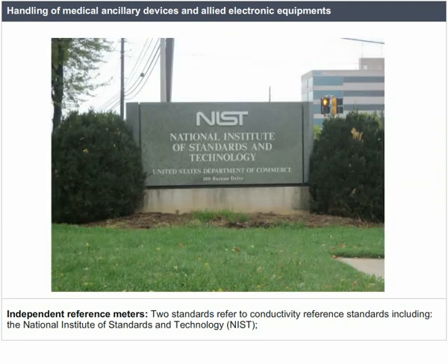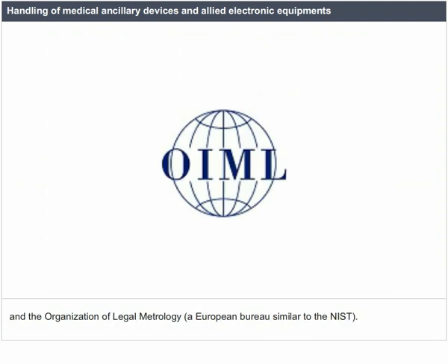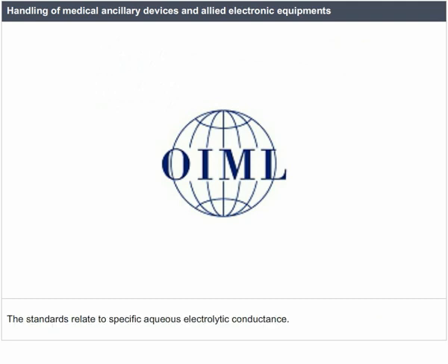Independent reference meters. Two standards refer to conductivity reference standards, including the National Institute of Standards and Technology, NIST, and the Organization of Legal Metrology, a European bureau similar to NIST. These standards relate to specific electrolytic conductance.